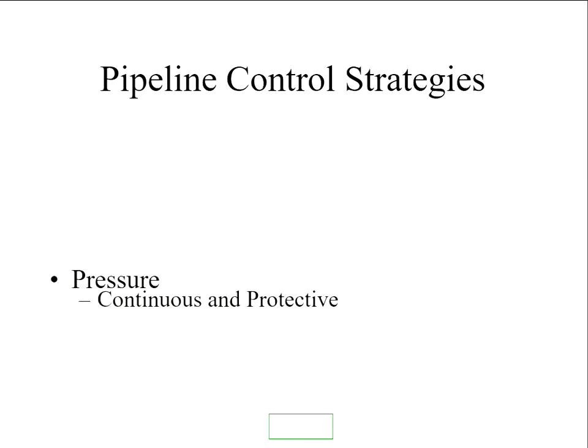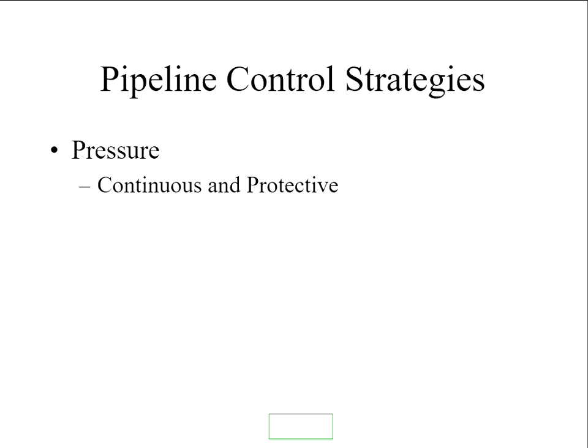So pipeline control strategies. The majority are, and I use pipeline in its broadest sense, so all the way down to local distribution mains, I'm not just talking high pressure here, under pressure control, and actually it's just continuous. So you have a set pressure that you desire to maintain at your source into the network, and it sits at that all the time. It's not managed, it's not varied over time.